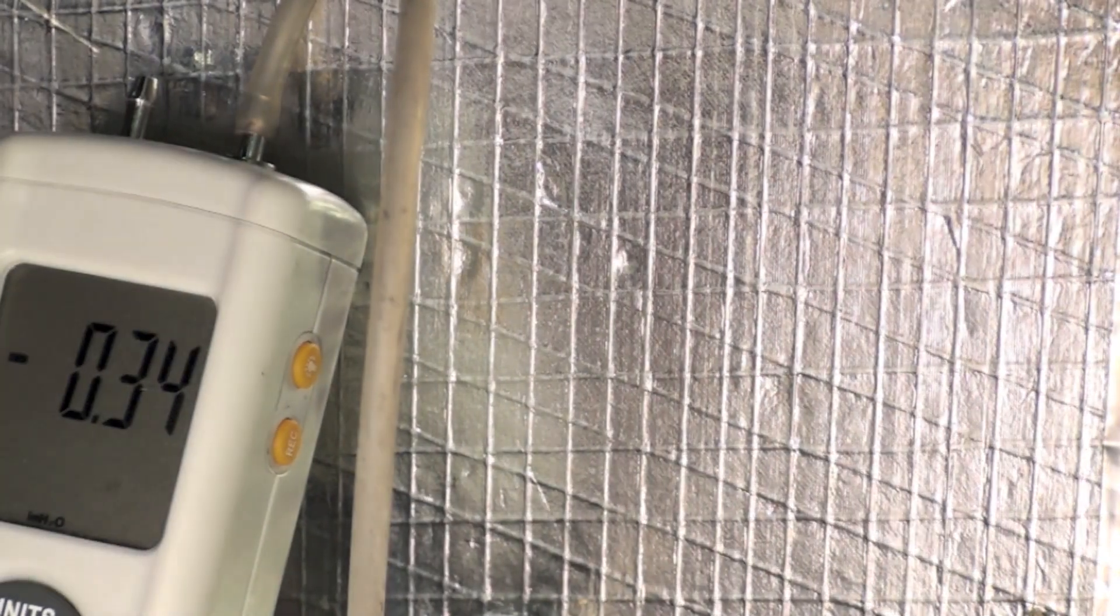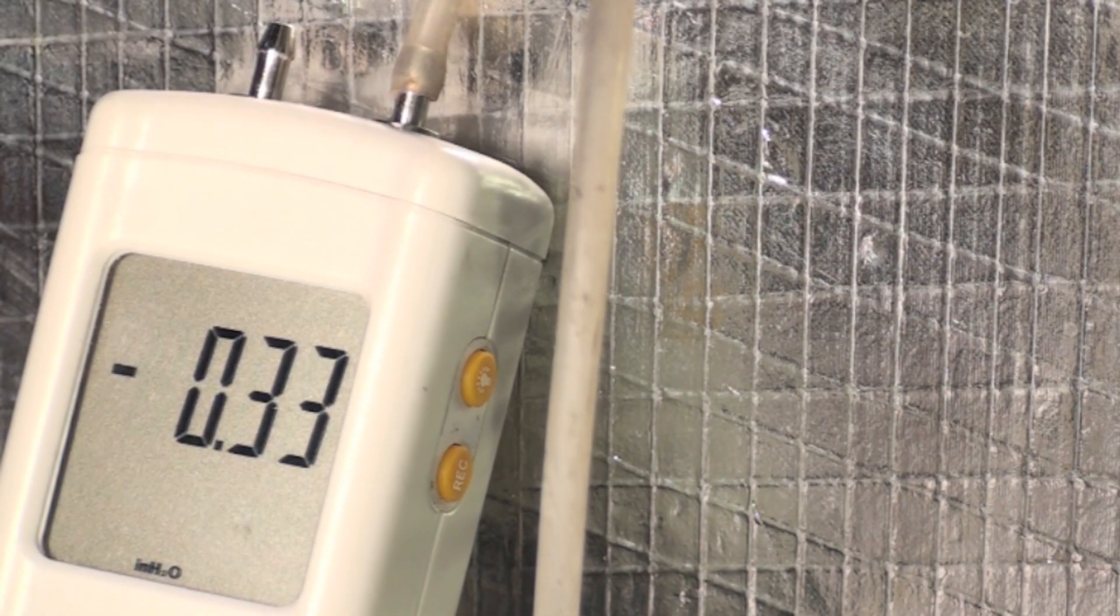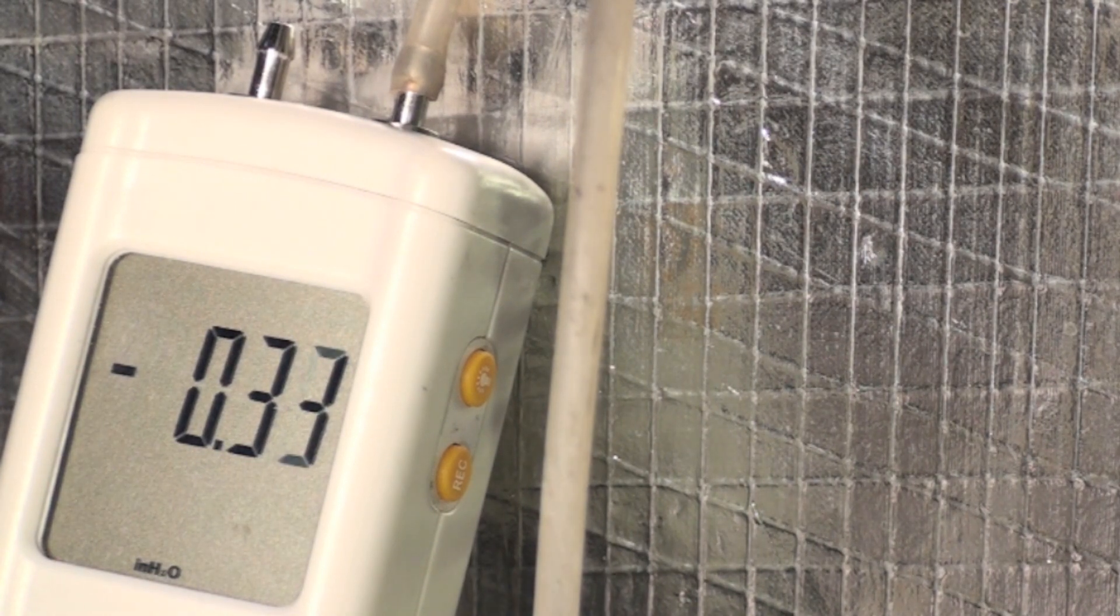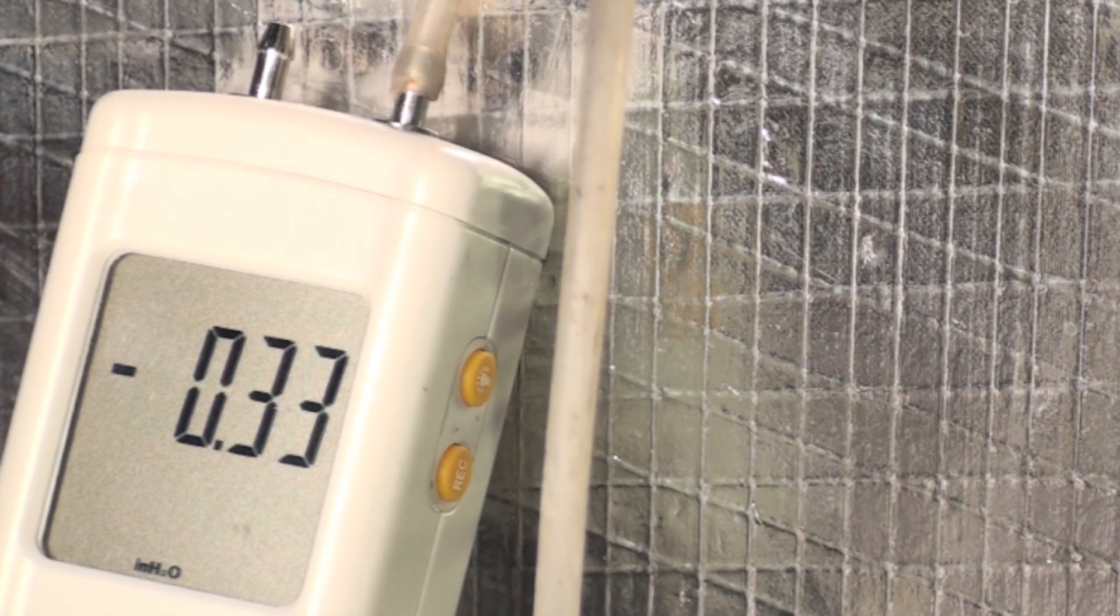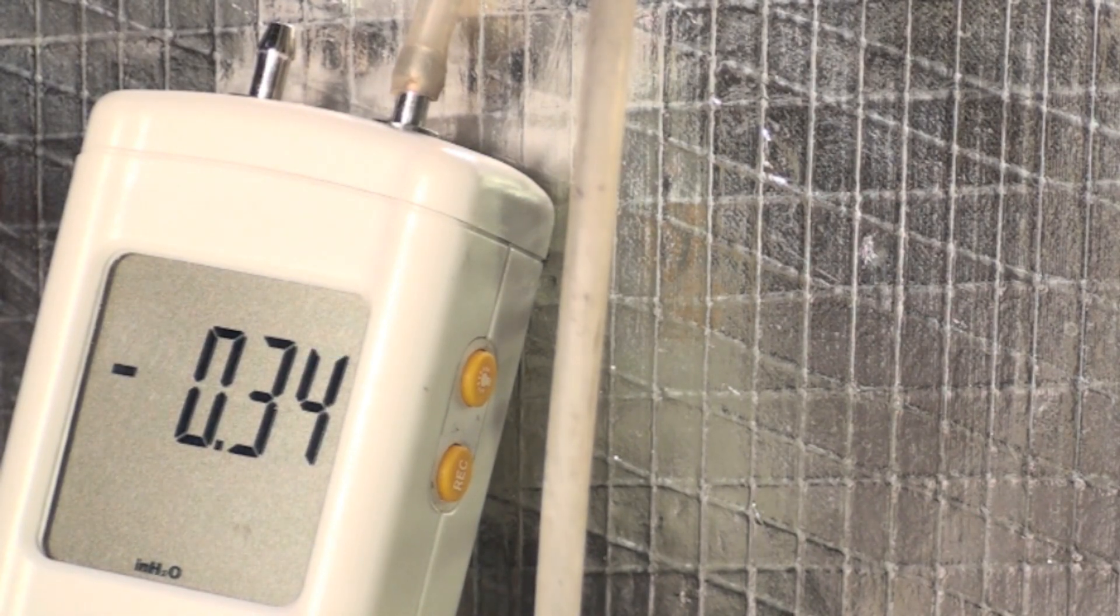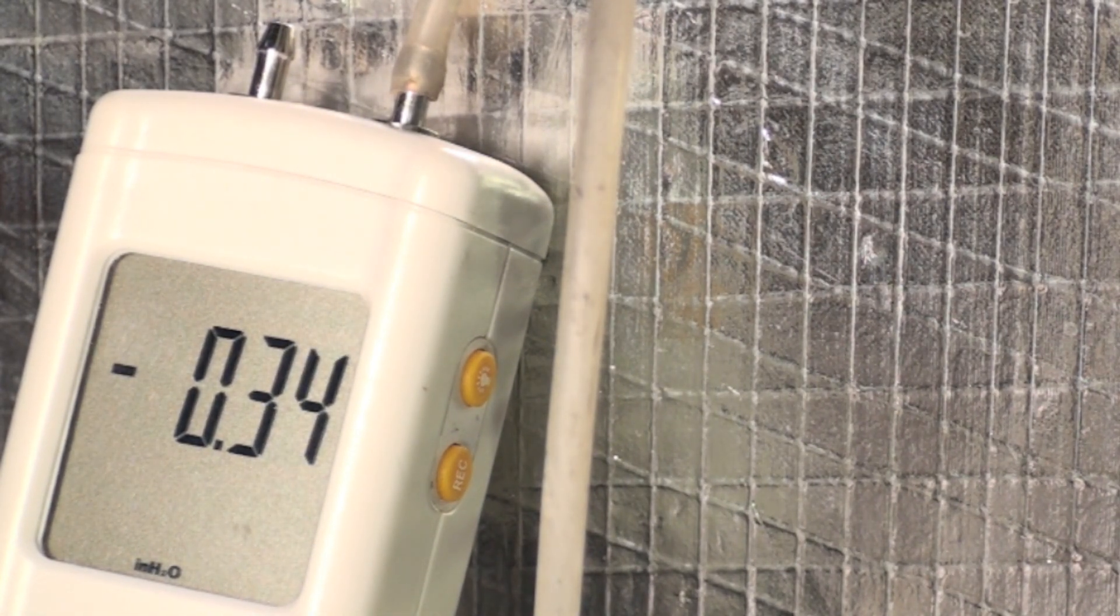I pulled that one line off and we're running about 0.34. So it looks like we've got more restriction in the return than we do across the filter. In the next one we're going to look at the positive pressures on the outlet side.